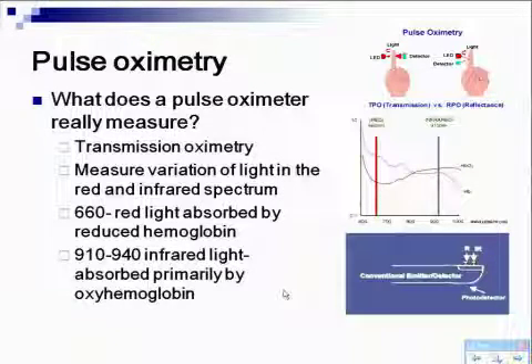The other problem with the pulse oximeter is that your finger is not a square tube. It's not a square ending. If you look at your finger, it's got a slope at the end of it. If the pulse oximeter is placed just at the end, it slips off because the patient moves slightly while sleeping, or the ventilator is moving and their fingers move a little bit. The pulse oximeter comes off, just a shave off, and all of a sudden the saturation begins to fall to 94, 95%, because what it's measuring is part of the environment saturation. So it gives you an erroneous reading.